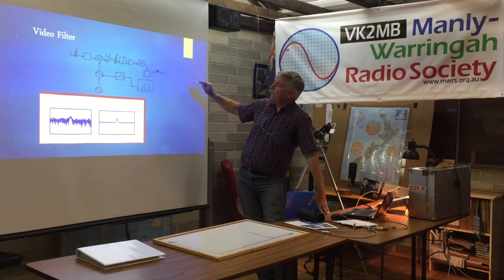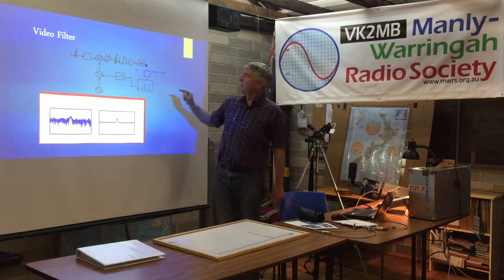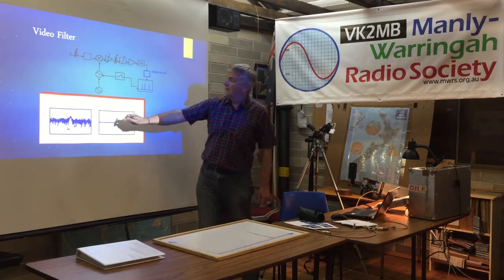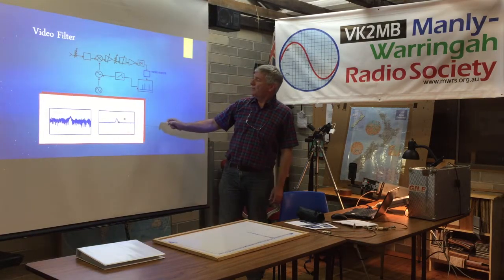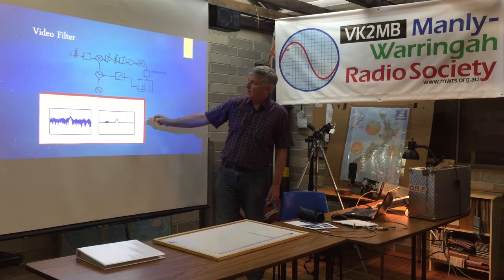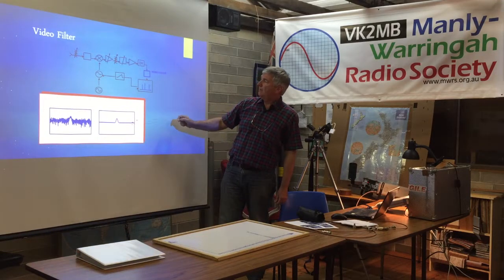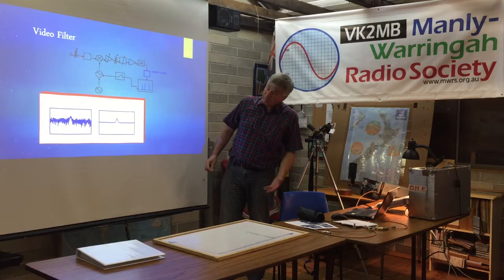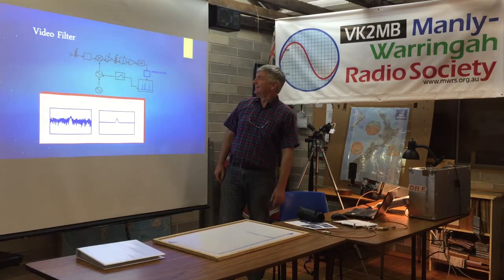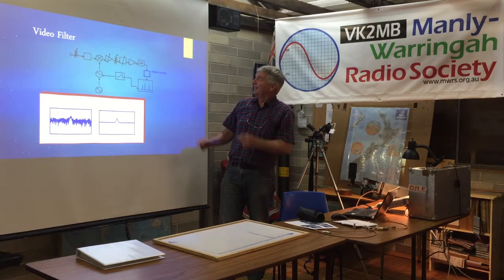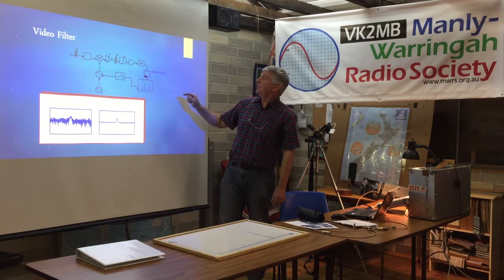And all this does is clean the noise up. So if you've got a noisy signal coming out of your detector, if you put the video filter in, it'll clean a lot of that noise off it. So it's photoshopping your thing. If you like, video shopping. And again, I guess that really should be drawn with an arrow through it too.